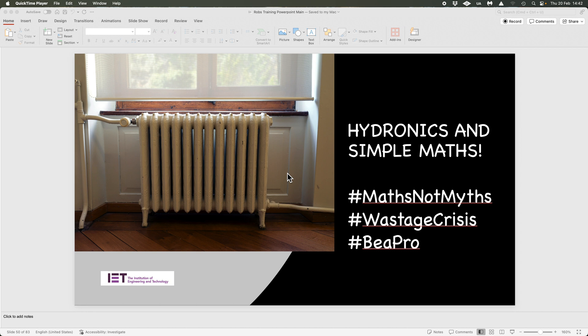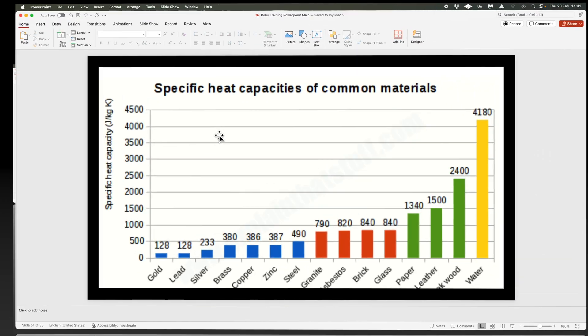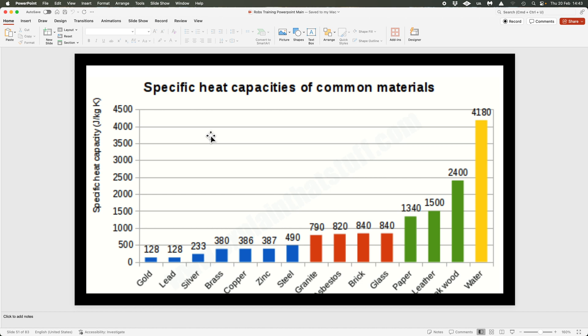This video is probably one of the most important calculations that any heating engineer really needs to know. So if we move forward and start talking about some basic properties we can get cracking on this. Specific heat capacities is something we need to understand. Looking through this list, you can see that water requires a very high level of energy to heat just one kilogram — it's about 4180 joules to heat one kilogram of water by just one degree. That's an awful lot of energy; it's one of the highest of any substance known to man.